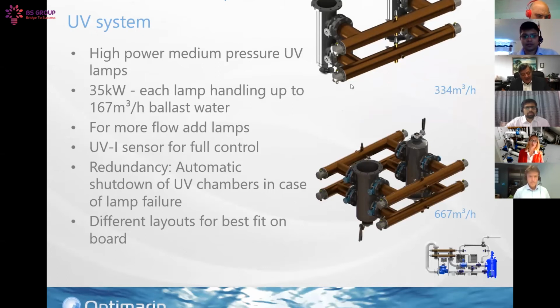So the UV lamps: each tube contains one lamp, and each lamp treats 167 cubic meter per hour. If you need a larger system, for example, this one is a 334 system, this one is a 667, you can also stack them on top of each other, so you have different ways to have a layout. And in case one lamp breaks down, these automatic valves close automatically, and then you reduce the flow and you can run over the other lamps. So there's a certain redundancy in the use of the system.